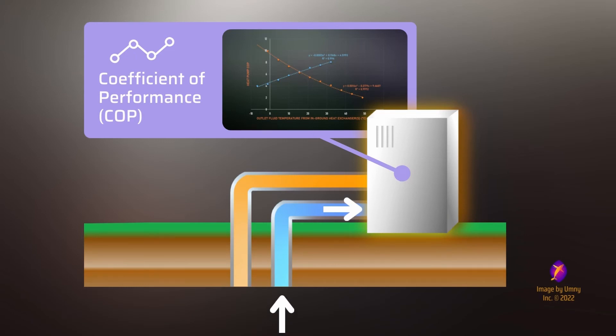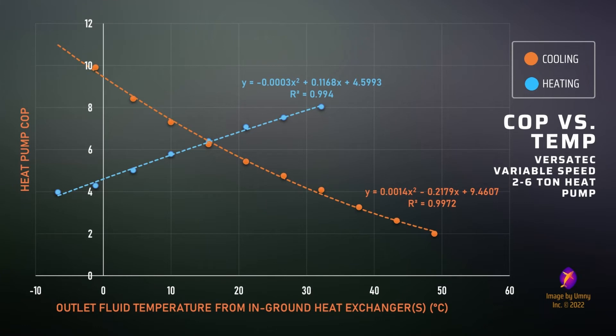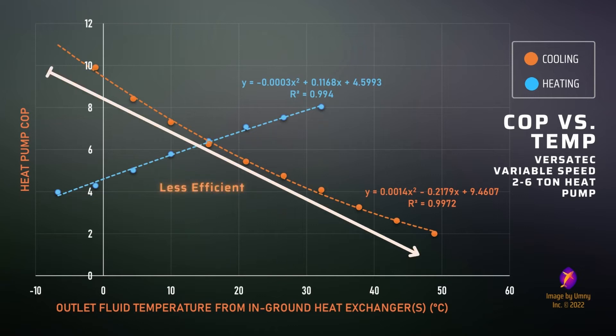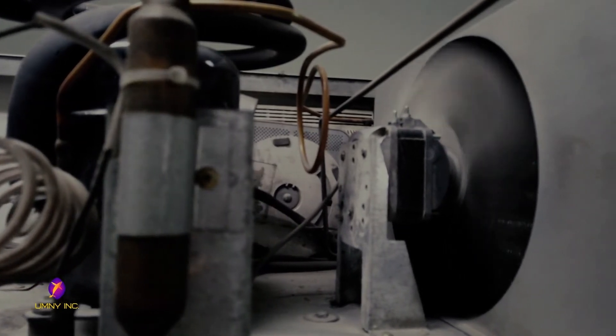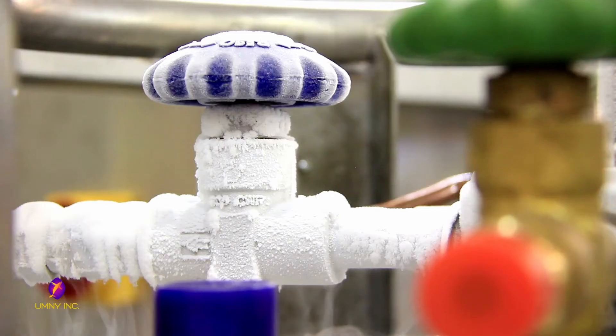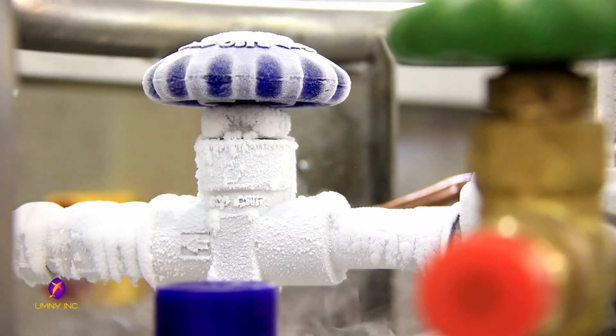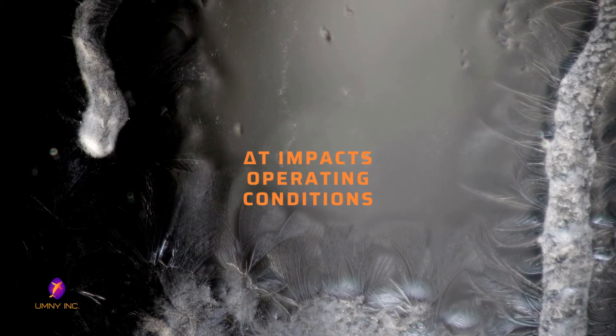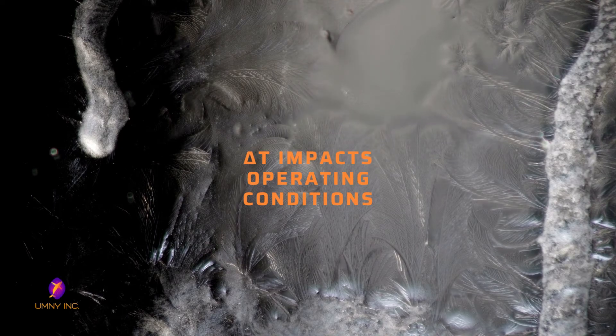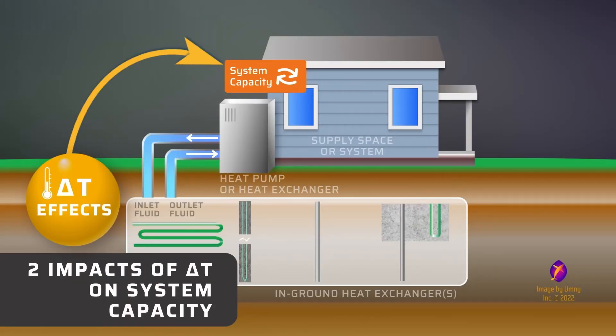Ground source heat pump manufacturers publish data in their manuals about the change in coefficient of performance as the fluid exiting the ground and entering the heat pump changes in temperature. This graph shows that the heat pump's efficiency in the heating mode reduces as the outlet fluid temperature from the ground reduces. Likewise, the cooling efficiency reduces as the outlet fluid temperature increases. All heat pumps have operating temperature limits, decided based on efficiencies, ability to transfer heat in the desired direction, and limitations of working fluids such as the freezing point of water. This means that a plus or minus 1 degree Celsius change in delta T can also move the system outside of a desirable operating range of temperatures.